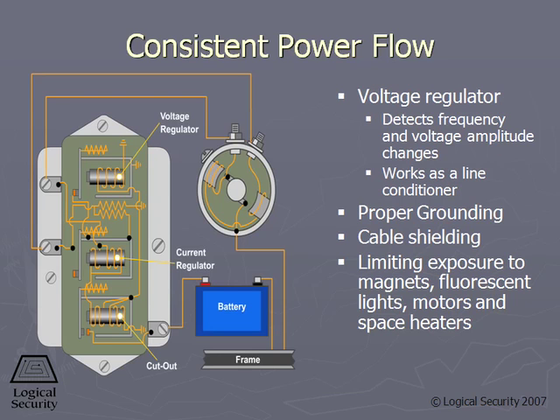This device is a voltage regulator. This may also be called a line conditioner. This protects against both overvoltage situations and undervoltage situations. They're fairly expensive and they quite often need to be repaired because they are high power devices. High power tends to overheat and these devices will degrade and fail over time.